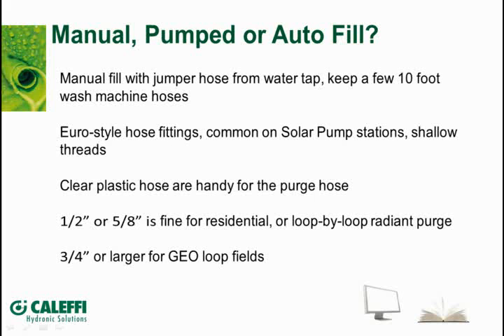I've got some little adapters I built that when I come across one of those, I just put a little metric garden hose adapter on it so I don't have a leak. Because the worst thing you want is to have the glycol start spraying out as you start pumping it in, because you're not sealed on the fill valve.